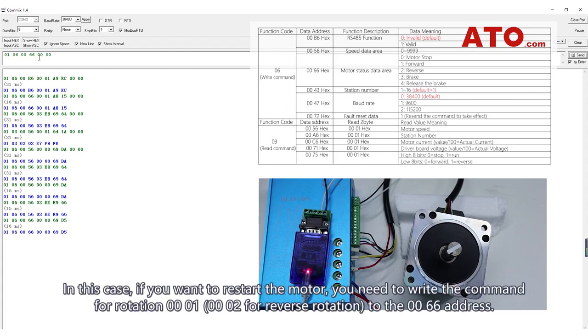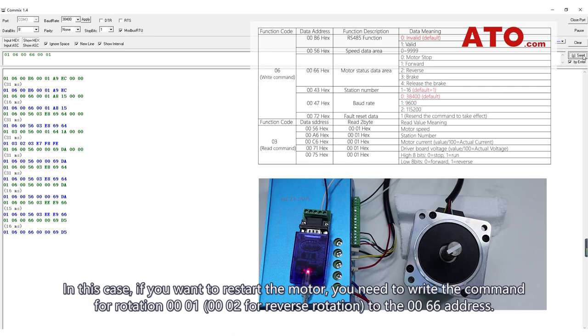In this case, if you want to restart the motor, you need to write the command for rotation 0001 to the 0066 address, and 0002 is meant for reverse rotation.